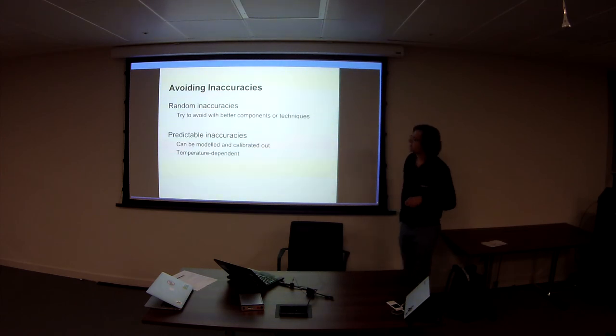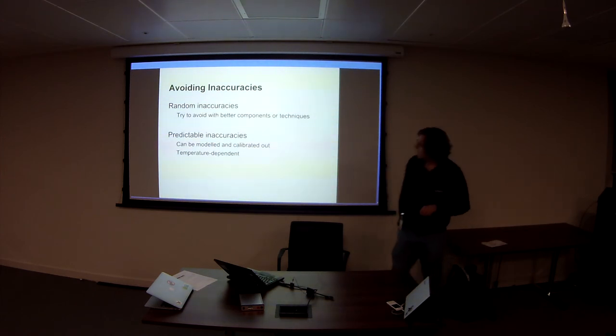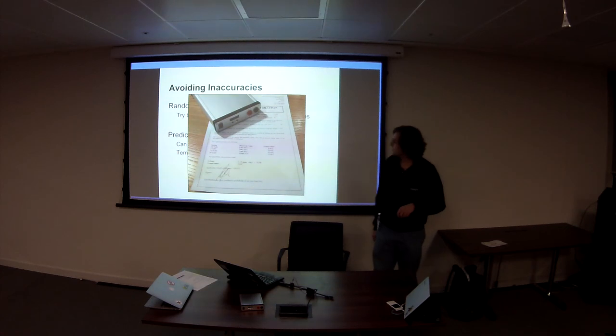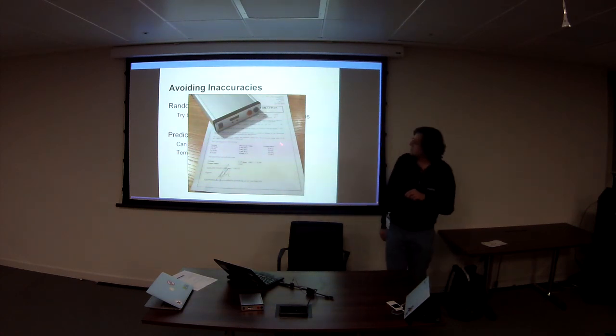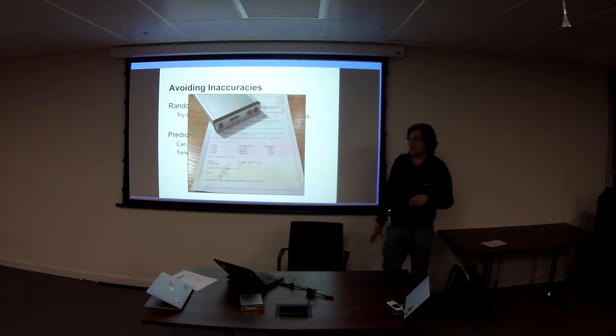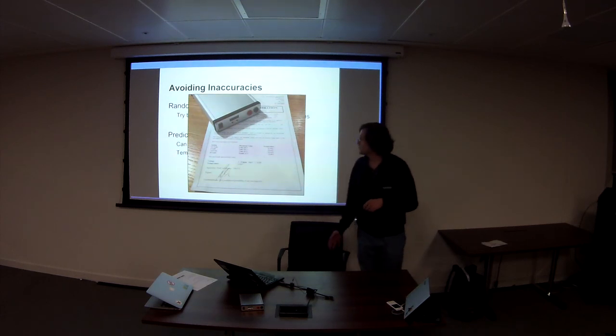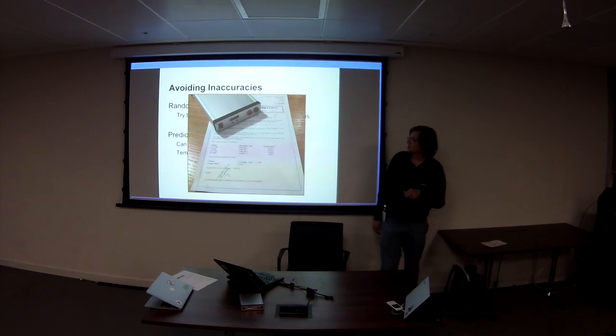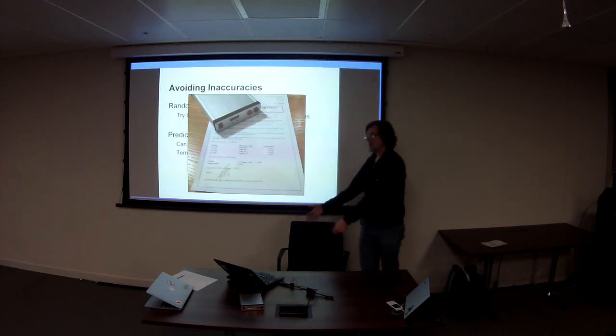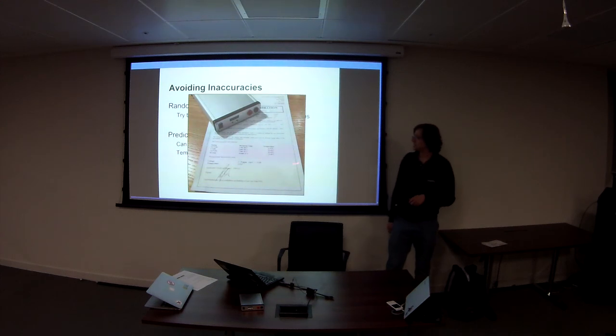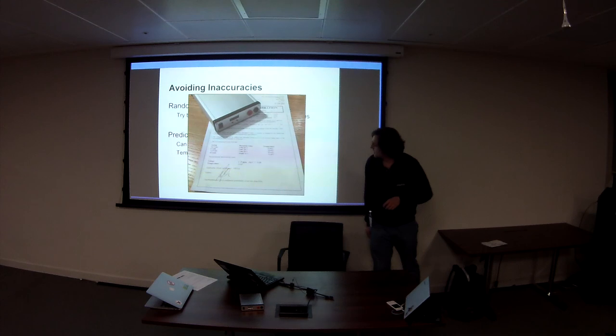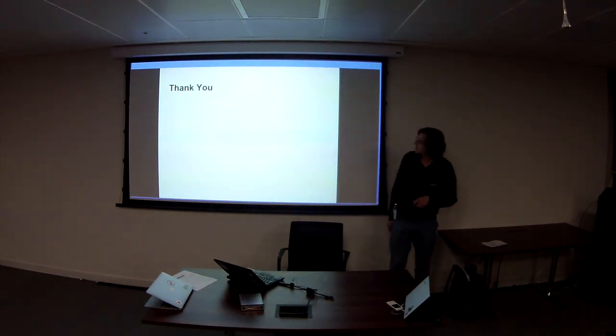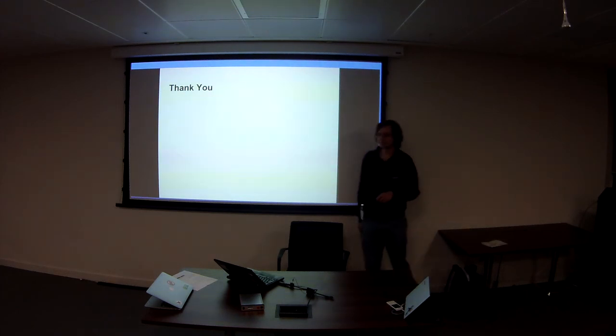A lot of them become temperature-dependent. And this is now my last slide. This is a calibration certificate that I got for the reference voltage chip, where they basically measured it. And they measured the temperature. Turns out this is very important. Because a lot of the inaccuracies and the offsets and things will vary with temperature. So suddenly you have to start playing games where you keep the thing at a constant temperature, possibly up to and including putting it in an oven that keeps it at a certain temperature to try and measure it and try and get these temperatures to whatever it's calibrated to. And then you get a sheet with all the details. And that's kind of it. Thank you.